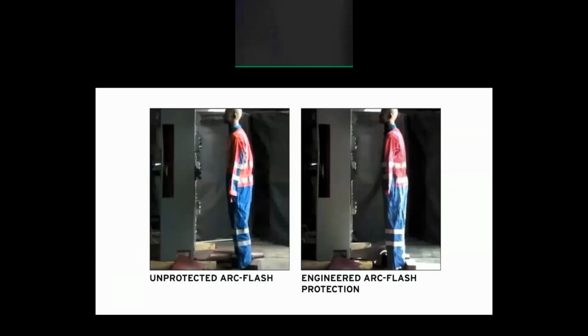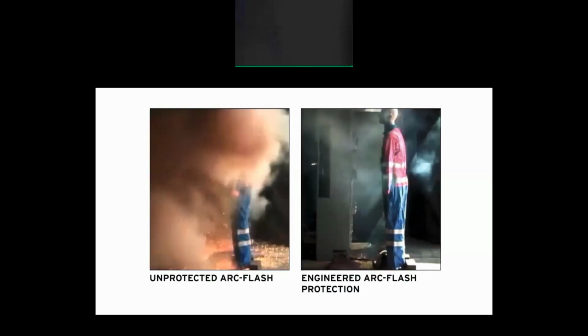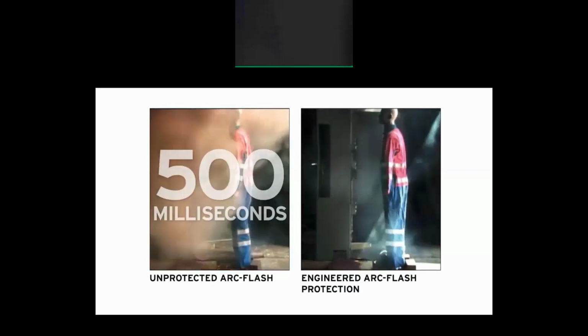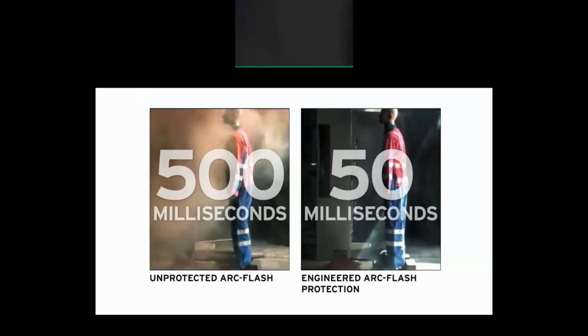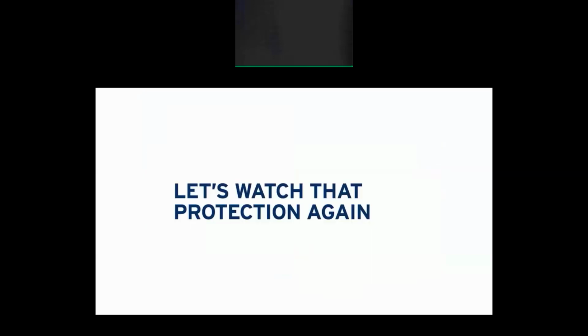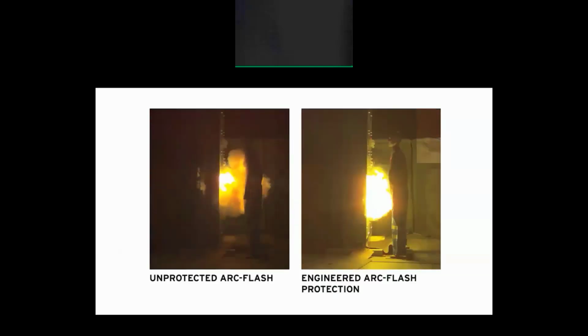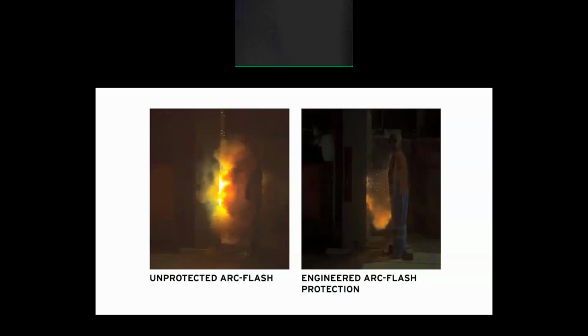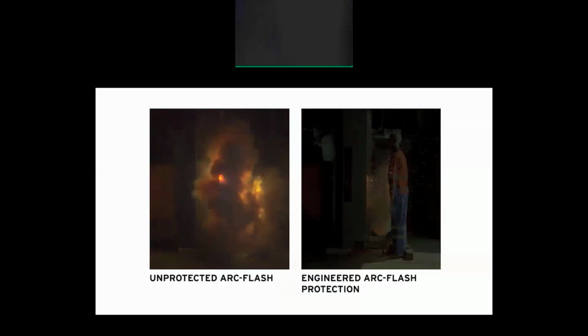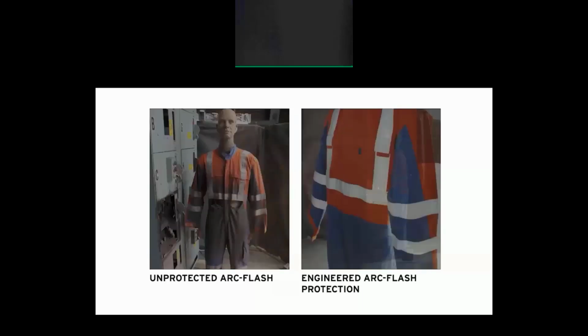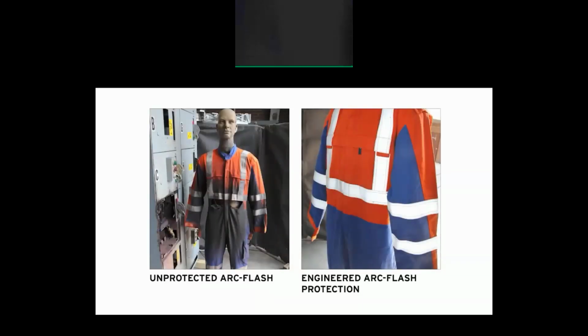Here we can see the purpose of a correctly operating trip circuit on the right. The control circuit can't prevent the fault, but as soon as we detect it and trip the circuit breaker, we can stop the flow of electrical energy into the fault. You can see that the energy fed into the fault on the right is much less, and we are better able to protect people and equipment.